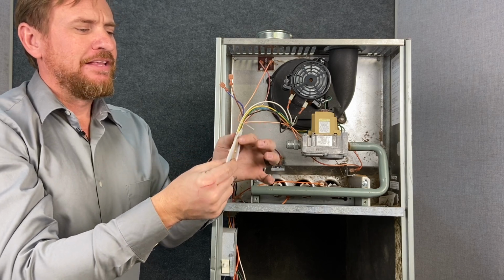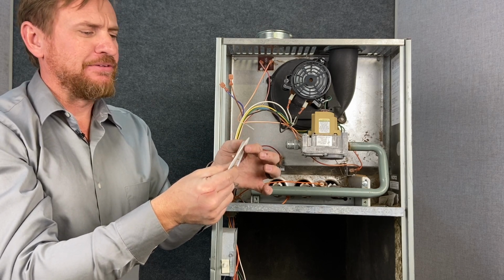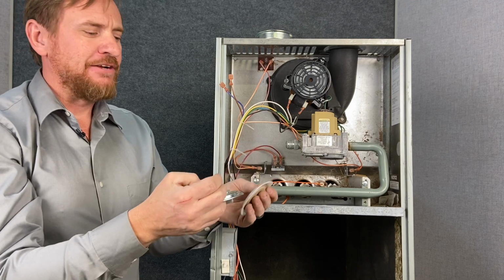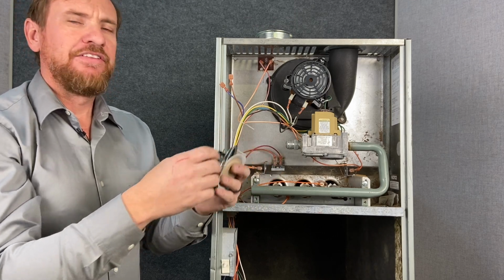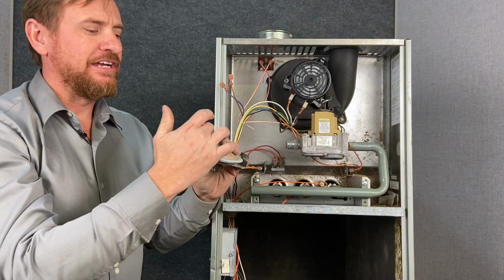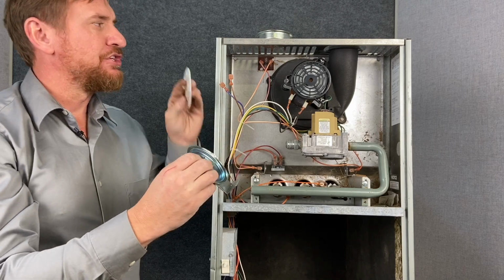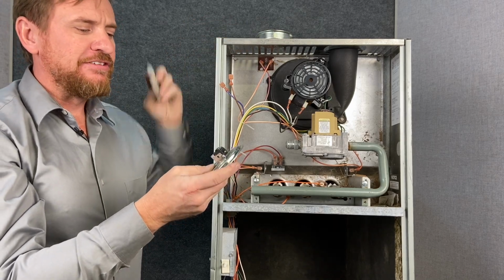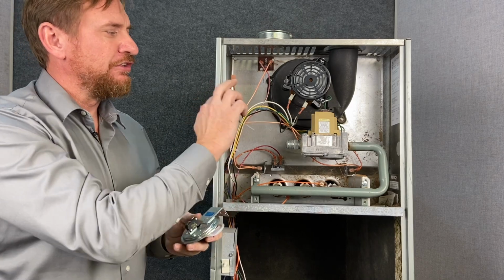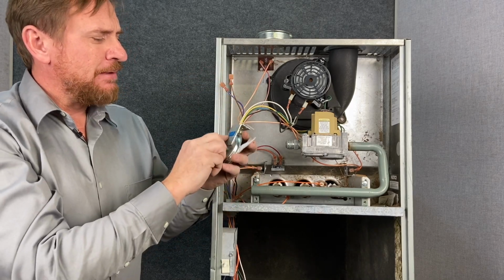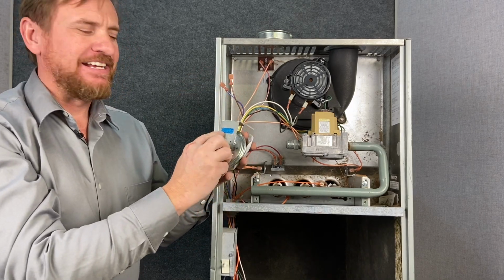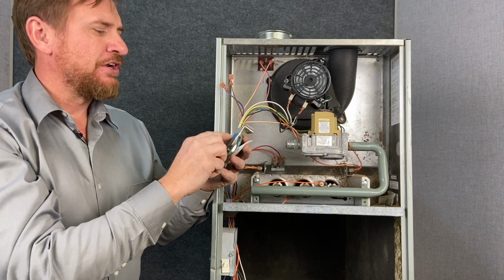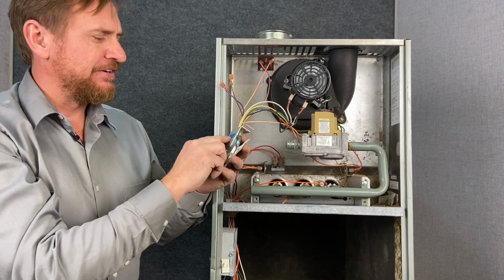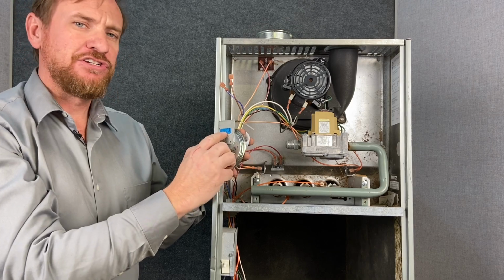But over time, this material, I don't know if it's some type of silicone, what it is, can break down. Or also, if you have the system installed incorrectly, you can get condensation up in here, and that moisture can cause issues. It's very simple to replace these. Just 1 hose, 2 wires, and 2 screws. But they all have very specific settings. They're measured in either inches of water column or water column pressure factor. This one's a 0.35 inches of water column.